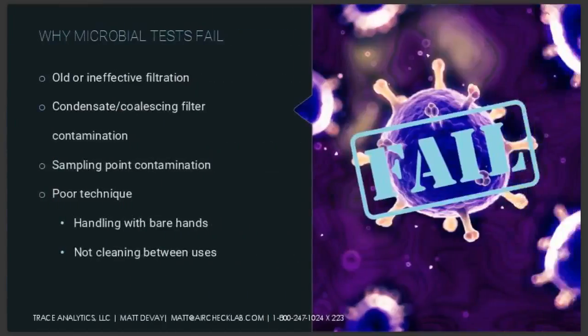So why does it fail? Well, once again, that filtration thing just keeps popping up. The only place in a compressed air system where microbes really like to grow tends to be in your condensate and coalescing filters. So your condensate traps, your coalescing traps and filters, those are the only places that are particularly habitable for microbes in your system. So just make sure you've got good particulate filters beyond that.